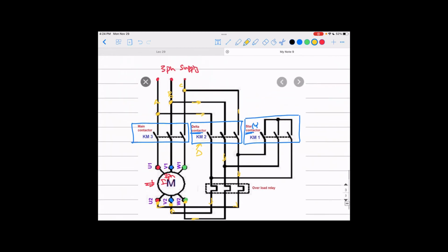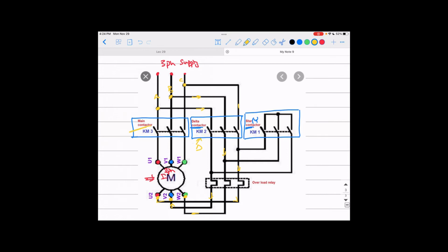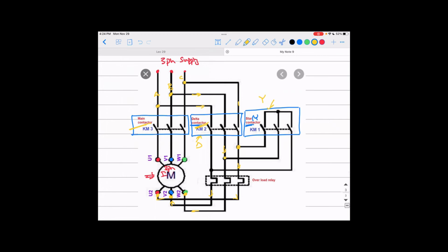Okay? That means from your lock in here, if you close the main contactor and the delta contactor, you're connecting this motor as delta. But what about the Y? Like you see in here, that is the Y contactor, and how it does this is you basically see the three phases of the motor connecting here. And if you close these switches, those are all closed, you are basically having a short circuit down here that's connecting those together. That's how we connect this as a Y: we have the three terminals of the motor connected together in one point, while the other three terminals are your line connection that you use for connecting to the supply. So if you want to connect this motor as Y connected, you basically close this Y contactor and the main contactor at the same time. Okay, guys?